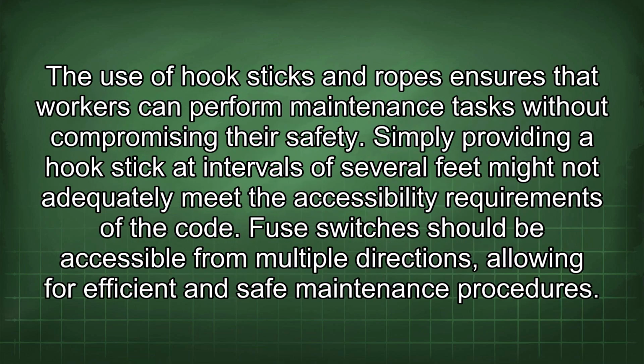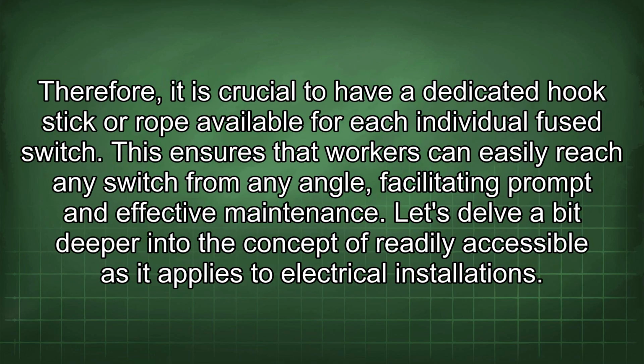The use of hook sticks and ropes ensures that workers can perform maintenance tasks without compromising their safety. Simply providing a hook stick at intervals of several feet might not adequately meet the accessibility requirements of the code. Fuse switches should be accessible from multiple directions, allowing for efficient and safe maintenance procedures. Therefore, it is crucial to have a dedicated hook stick or rope available for each individual fuse switch. This ensures that workers can easily reach any switch from any angle, facilitating prompt and effective maintenance.